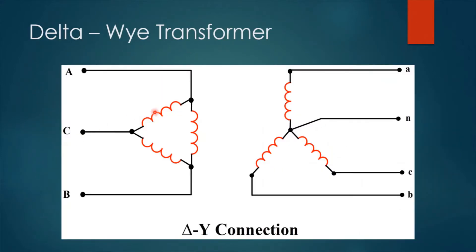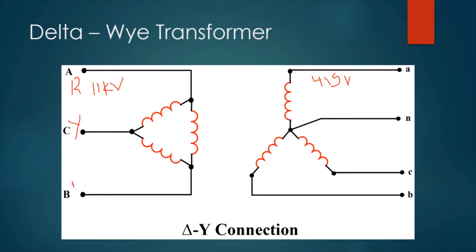The delta-Y transformer is connected with the primary side in a delta shape and the secondary side in a Y shape, which is exactly what we need for a distribution system. For example, assuming this is an 11 kilovolt to 415 volt transformer, the primary side will be 11 kilovolts and the secondary side is 415 volts. The primary side is connected to the medium voltage cable, which has three phase cores: R, Y, and B.